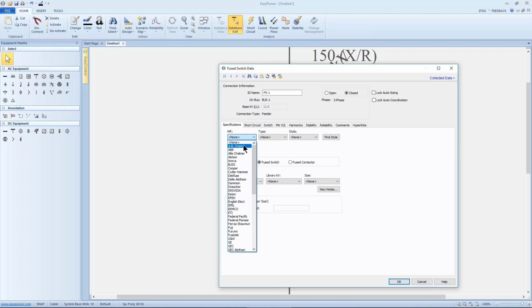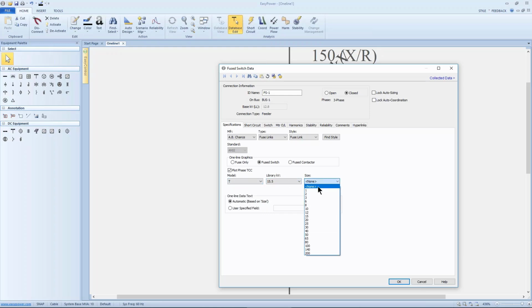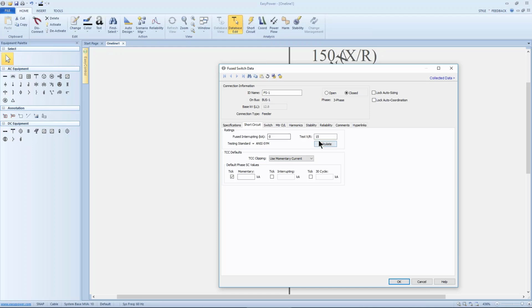He said, Jim, this label on this fuse says it's an AB Chance. The type is a fuse link. The style is a fuse link. The model on the label says it's a Model T, and we both chuckled because we thought of a Model T in a different context. And it's a size 10. Now what I want to do when I go to short circuit is see one or both of these numbers change when I click calculate.